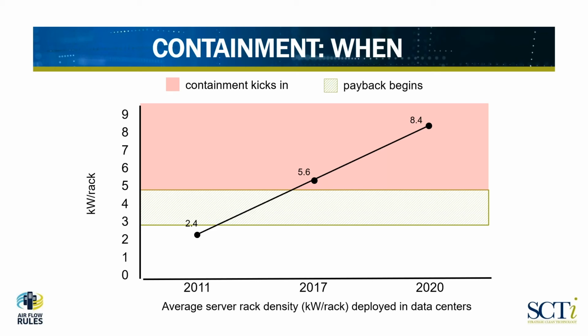However, in some architectures, especially now with folks using outside air and slab floors instead of raised floors, you're sort of obligated to do containment in order to manage the room at any density. So sometimes the site architecture will dictate it, but one of the case studies we'll show later had a 2-year payback across several sites with an average density of 2 kilowatts. But that was because the cooling units were really old and inefficient or way over provisioned. So it is site specific, but generally that 5 kilowatt rule of thumb is where we see most co-location providers in the States.